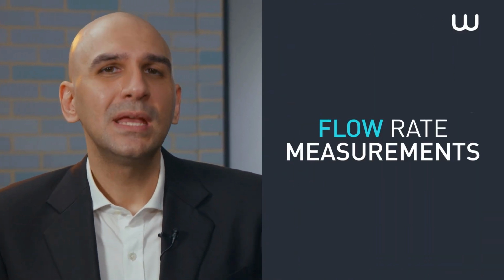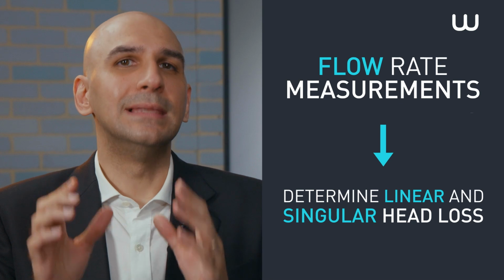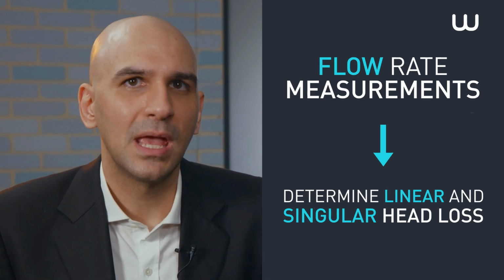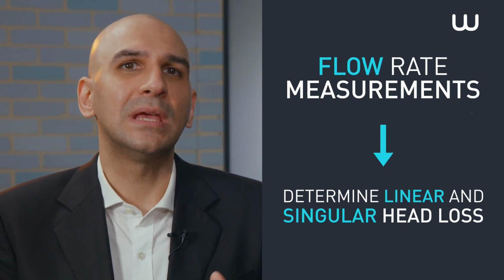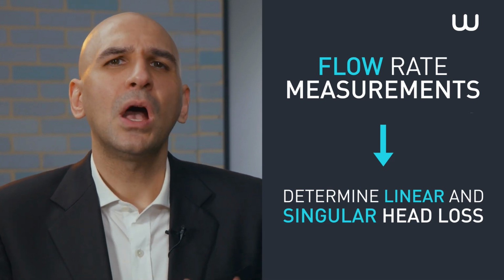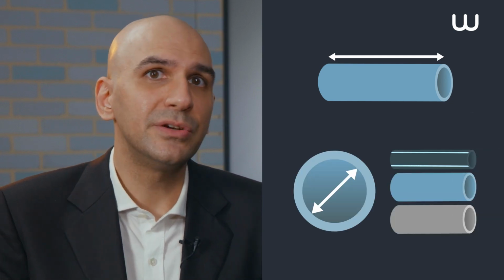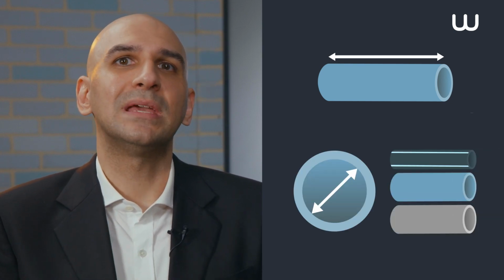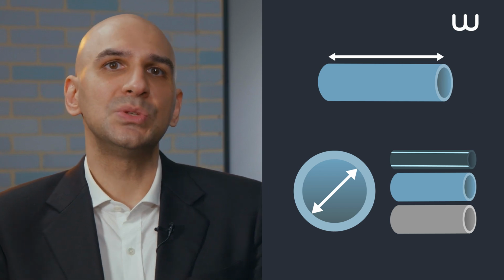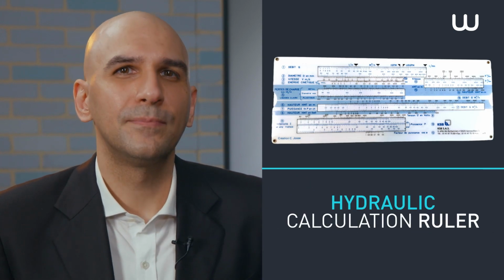Along with flow rate, the total dynamic or manometric head, TDH, is another major parameter to be determined during an audit at a pumping site. After having measured flow rate, it will be possible to determine linear and singular head losses, values that are required to calculate the total dynamic head. Other data, such as an internal pipe's length, inside diameter, and material, will be needed in order to calculate these head losses, namely using a hydraulic calculation ruler.